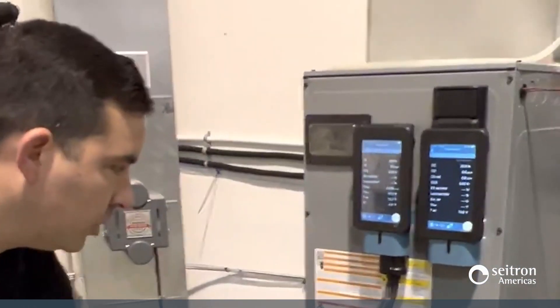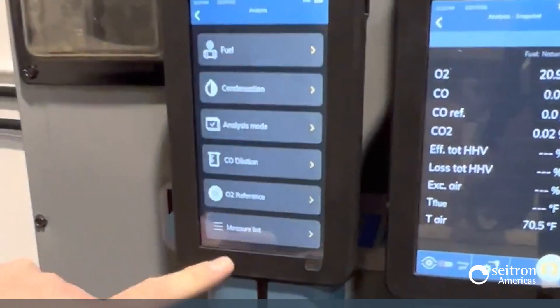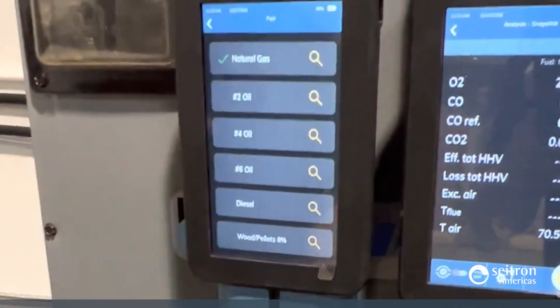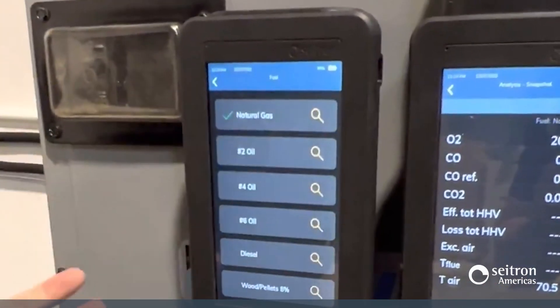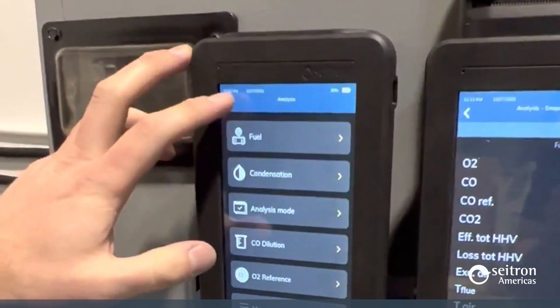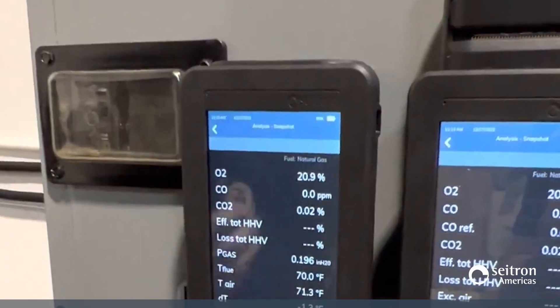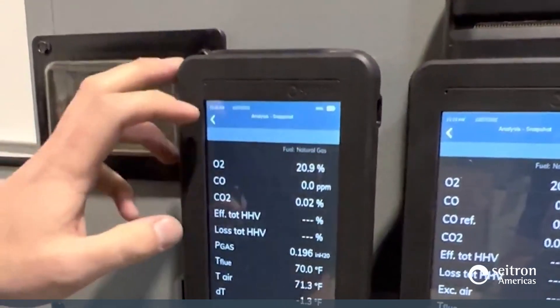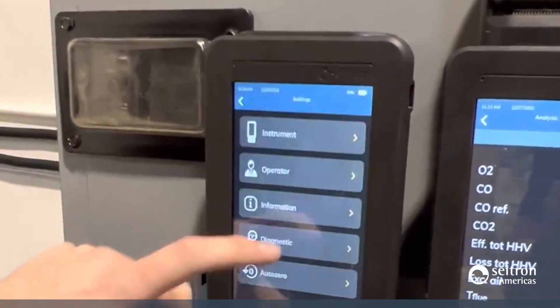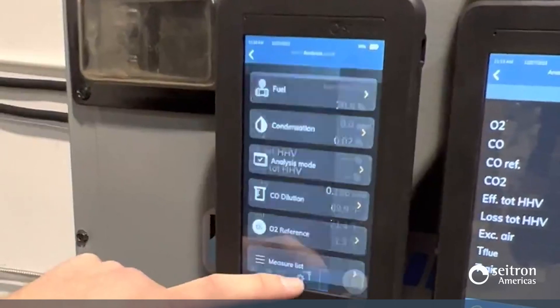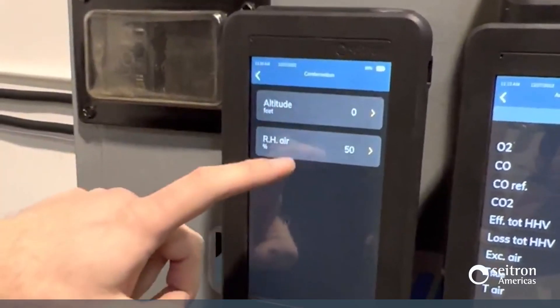One of the next things to do is set our fuel selection. On the analyzer, go to Settings, then select Fuels. Depending on whether we're doing natural gas, oil, or propane, there are various pre-installed fuels to select. This selection will tweak our carbon dioxide as well as our combustion efficiency readings. For high-altitude areas, you can also set the altitude settings within the analyzer so you have the ability to adjust your readings in a high-altitude setting.